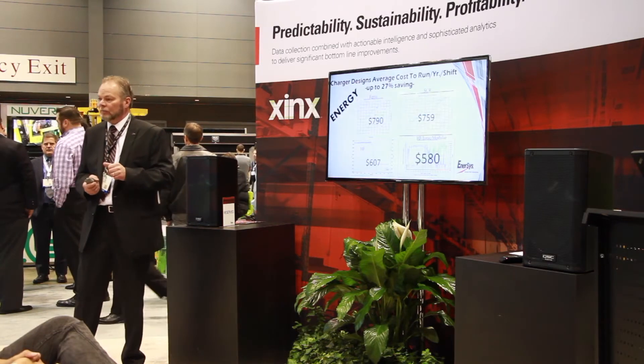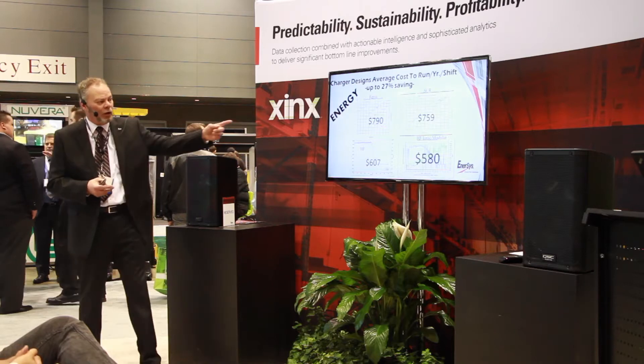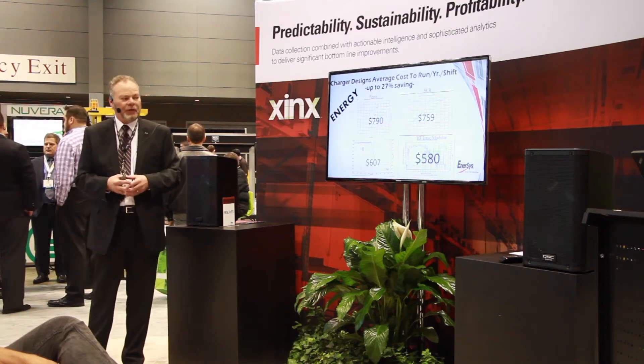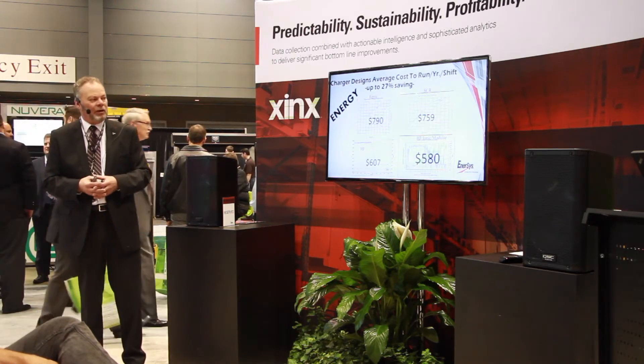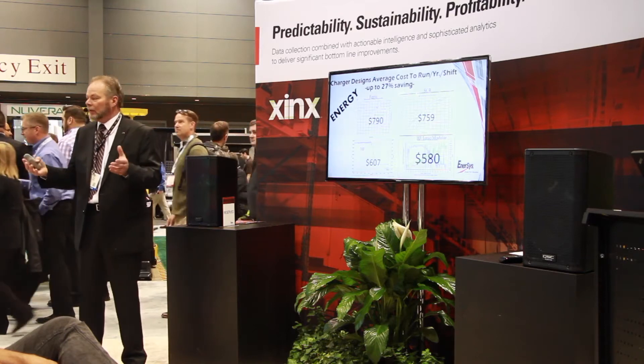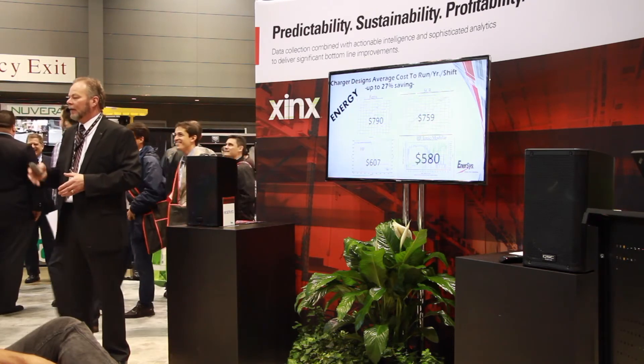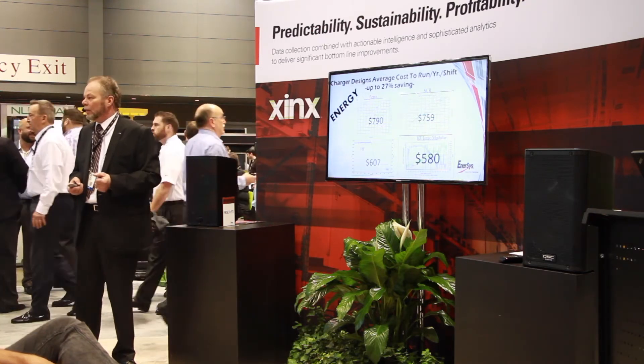Comparing charger running costs for one year on one shift: the ferroresonant charger cost about $790; SCR was $759 — not much different; HF was $607; HF modular was $580. So if you run a three-shift operation, there are some pretty good savings. If you walk into a building with old-style transformer chargers, you can save $200 to $300 per charger just on your electric bill by replacing them with a high-frequency modular unit — a big savings over the expected 10-year life of a charger. It'll pay for itself quite easily just in electricity costs.